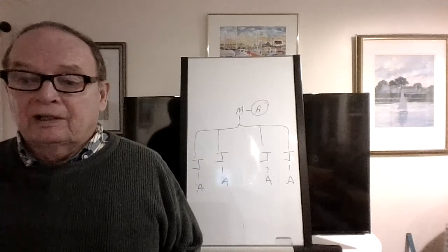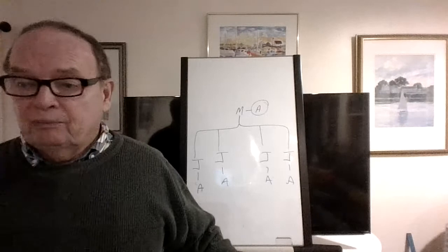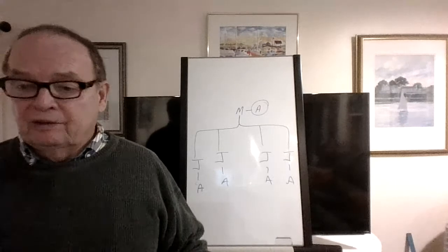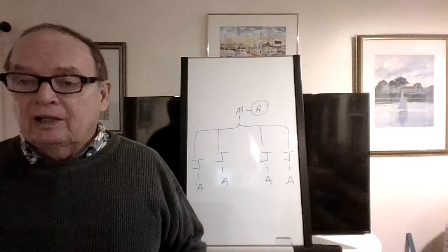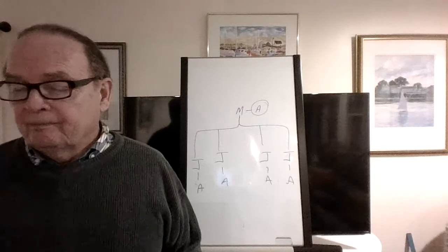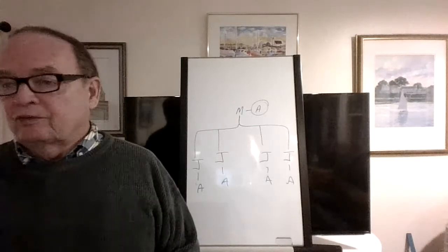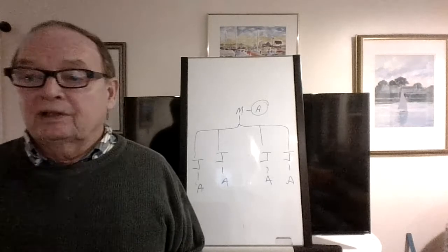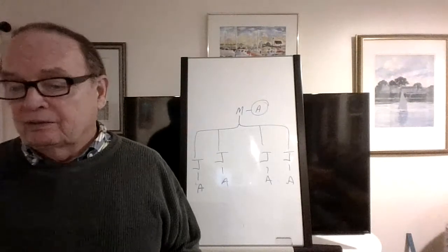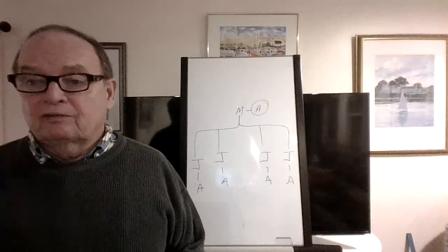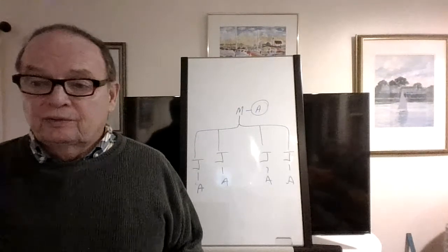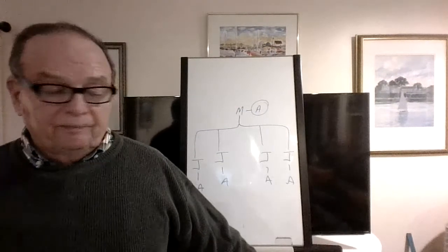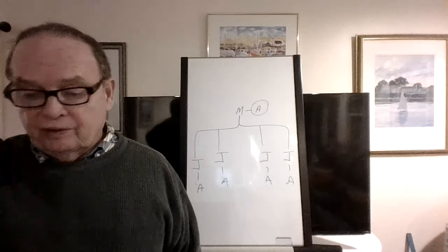Now, for those of you who haven't done it, you just cap all the pipe that you're putting underground. It's all exposed so it can be inspected. And then you have maybe a 2-inch pipe, and you brace it so it doesn't fall over, whether it's no hub with a gasket or a piece of PVC, if it's some kind of residential. And you brace it so it doesn't fall over. Fill it up with a hose, right? You can fill it up from down below, or just put the hose in the top.